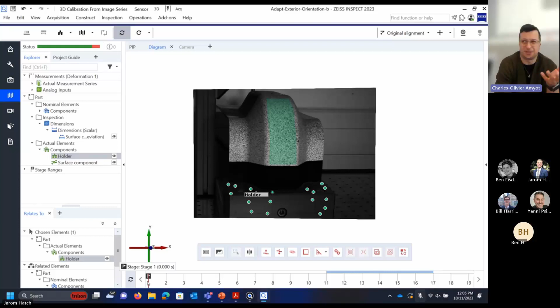So this function is going to be really good, more for troubleshooting and for high-speed imaging, but it might also have an impact if you're doing long-term testing, depending on your use cases. If you're not using a system for a while and you want to keep the same volume, you can readjust it, because somebody might have touched it, or you come in the next morning and there's maybe a little bit of decalibration. Without having to redo a full calibration, you could just take a picture of your calibration object to reset things.